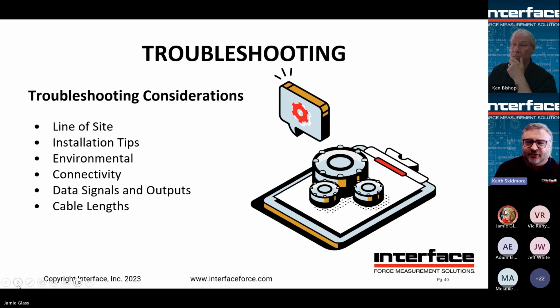Troubleshooting, when the system isn't working well. It's not always obvious with lifting. Sometimes it's relatively easy to pick up something of relatively known weight and see if it's measuring correctly. That may be easy enough to do. You may not have anything you can lift, though, that you know what it weighs. But again, in troubleshooting, you have, say, wireless systems. You have line of sight issues. Wireless likes to work line of sight. It will bounce around, but you may or may not get signal with wireless.